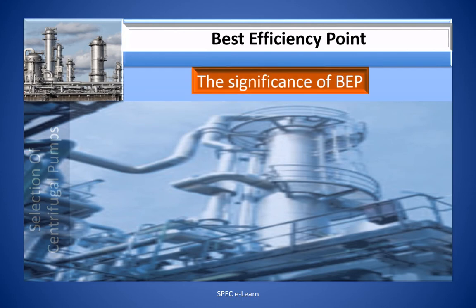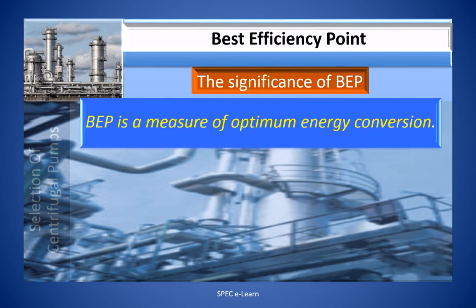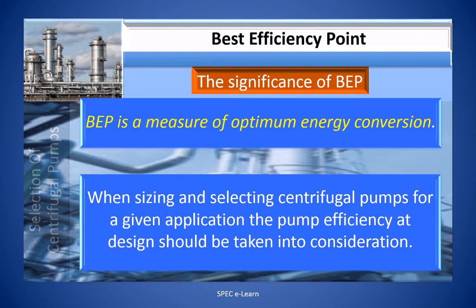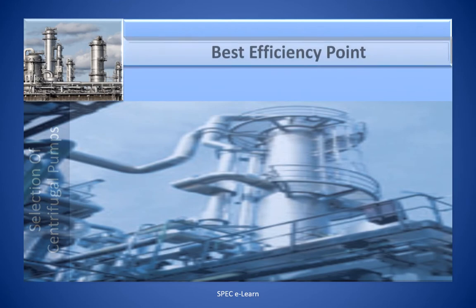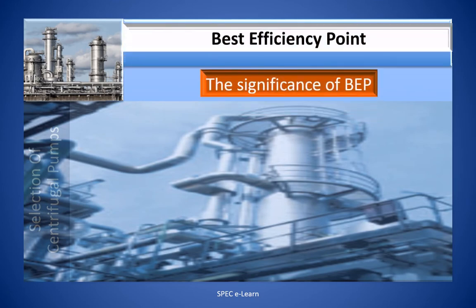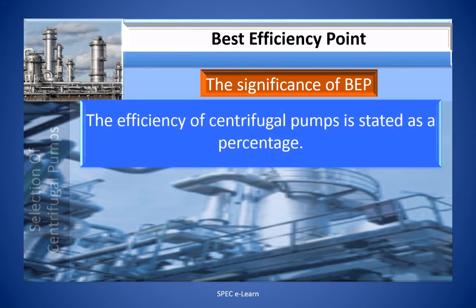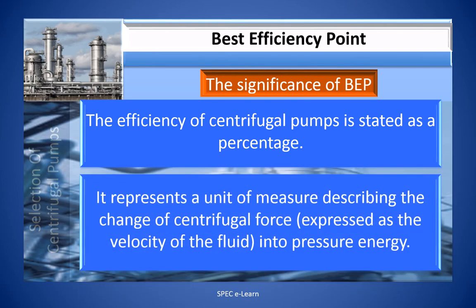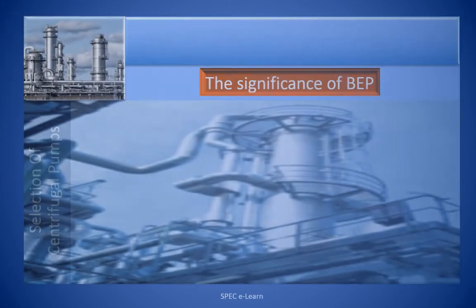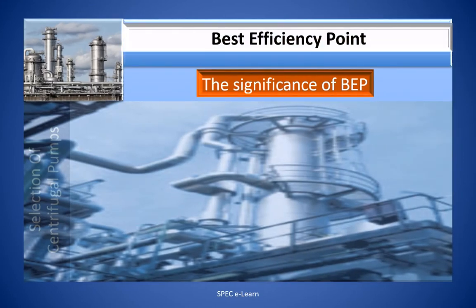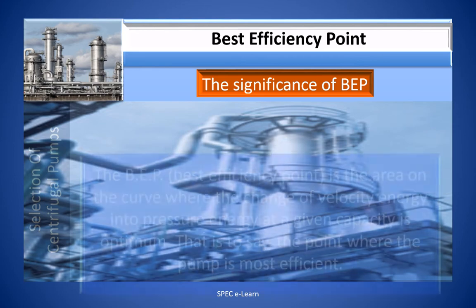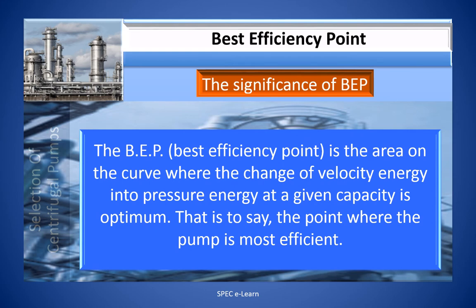BEP is a measure of optimum energy conversion. When sizing and selecting centrifugal pumps for a given application, the pump efficiency at design should be taken into consideration. The efficiency of centrifugal pumps is stated as a percentage, representing the change of centrifugal force — expressed as the velocity of the fluid — into pressure energy. The best efficiency point is the area on the curve where this conversion at a given capacity is optimum; in other words, BEP is the point where the pump is most efficient.